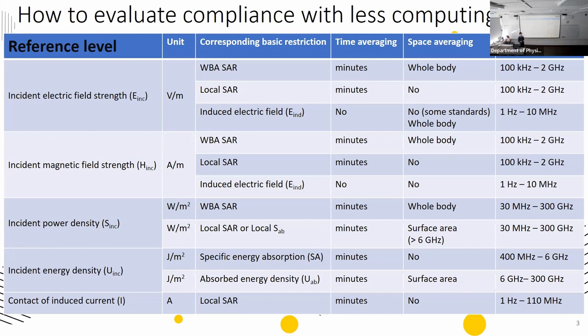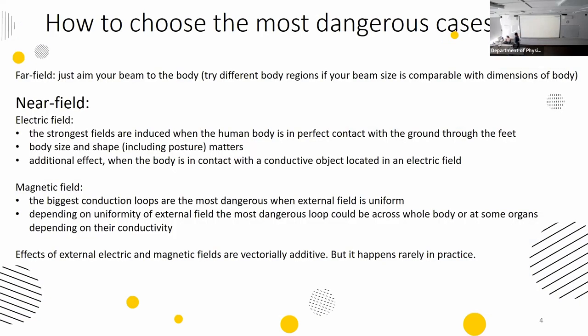But how do you choose worst cases for different types of human bodies and device positions? For far-field devices it's fairly obvious — you bring the radiation source close to the body — but you still need to try different body regions. For different frequencies you don't know whether to bring your radio device to the head or to the limbs, because limbs and heads have different restriction levels and different conductivity and tissue properties, so the field distribution could be different too.